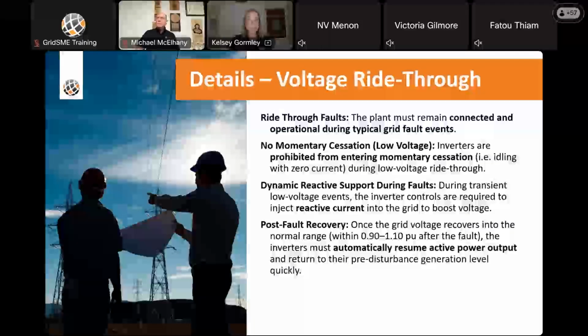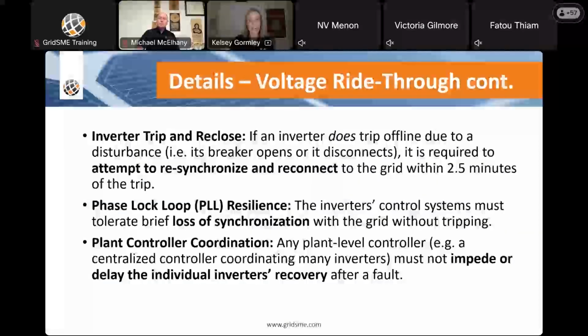We'll move on into the next section. If an inverter does trip for, again, voltage ride-through, it is required to attempt to resynchronize and reconnect to the grid within 2.5 seconds of that trip. The only exception is if the trip was caused by a hardware or internal failure, like a fatal fault, in which case immediate reconnection might not be possible. This requirement ensures that transient trips are not permanent and that the resource should come back and support the grid as soon as it is safely available to do so.